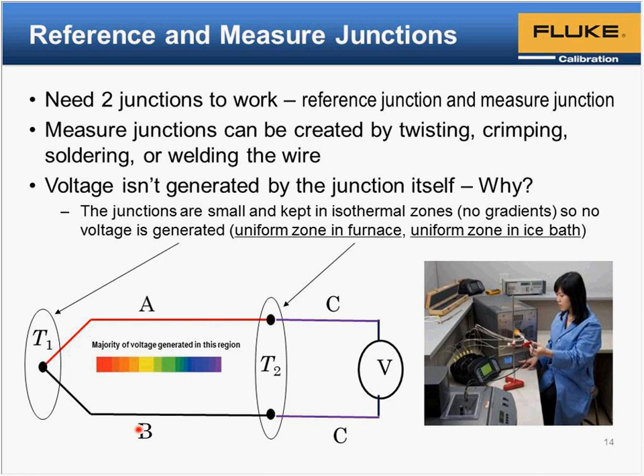So if you put the thermocouple in a furnace, and the furnace is uniform temperature-wise, in the bottom of the furnace where the measuring junction 1 is, there isn't much voltage generated by the wire in that region. Where the voltage is generated is at the top of the furnace, where it transitions from room temperature to the temperature of the furnace. The reason why this is important to think about is that this is also where there's a good chance that the wire is changing composition, because maybe the temperature where the wire transitions into the furnace is an oxidizing temperature.